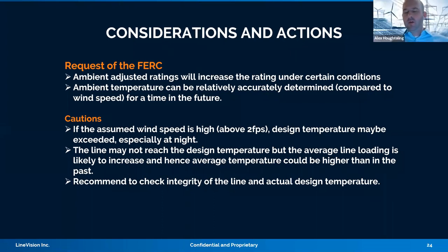That makes a lot of sense, Rob. It reminds me of a study from the Department of Energy that found a 5% increase in capacity reduces congestion by 60%, and a 10% increase nearly eliminates that congestion. Individual circumstances apply, but the values we're discussing seem sufficient to allow for that congestion reduction, even with limiting factors within the substation. Again, specifics apply - you need to be certain it's thermal rating limited, not stability or voltage limited.